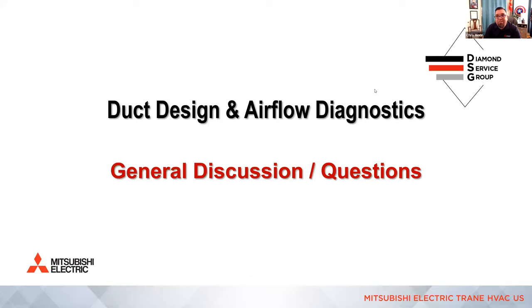So yeah, I'm going to be honest though, that's a tough one. Obviously you want to do this after you install the ductwork, and I think it's not done correctly enough to trust sometimes as an HVAC contractor. But if you do it right, it adds such a higher level of R-value to that duct system that it's such a great thing. I've seen people spray foam duct systems too, and they don't do it right, and you end up with these voids and moisture and stuff. It's unfortunate.